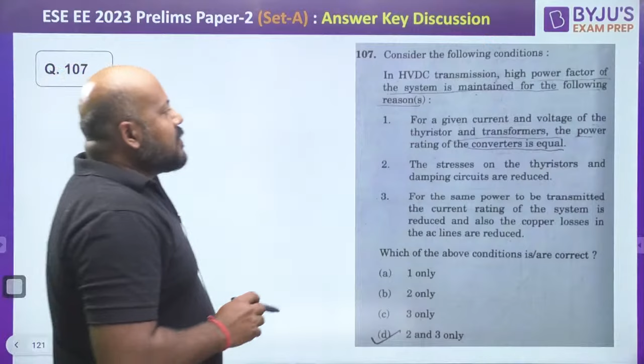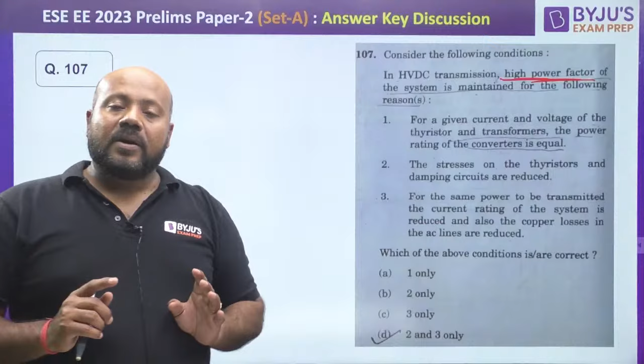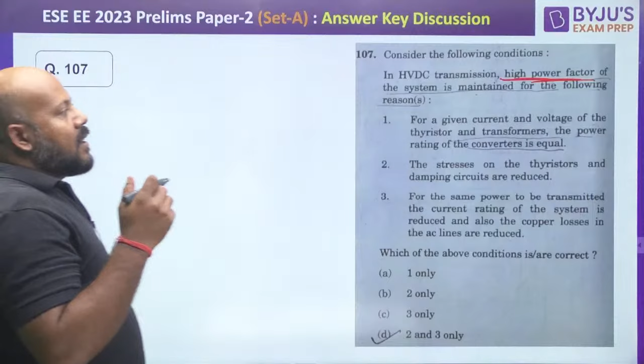There are two reasons. Number 1, if you go to the AC side of the HVDC, you require reactive power compensation. If you go to the DC side, there is no actual requirement of reactive power compensation, but at the HVDC converter station, because of the presence of converters, inverters, or power electronic devices, you require reactive power support. For that purpose we always want our operating power factor to be high. Now what is the conclusion? For a given current and voltage of the thyristor and transformers, the statement says the power rating of the converter is equal - this is actually wrong, it should be more.